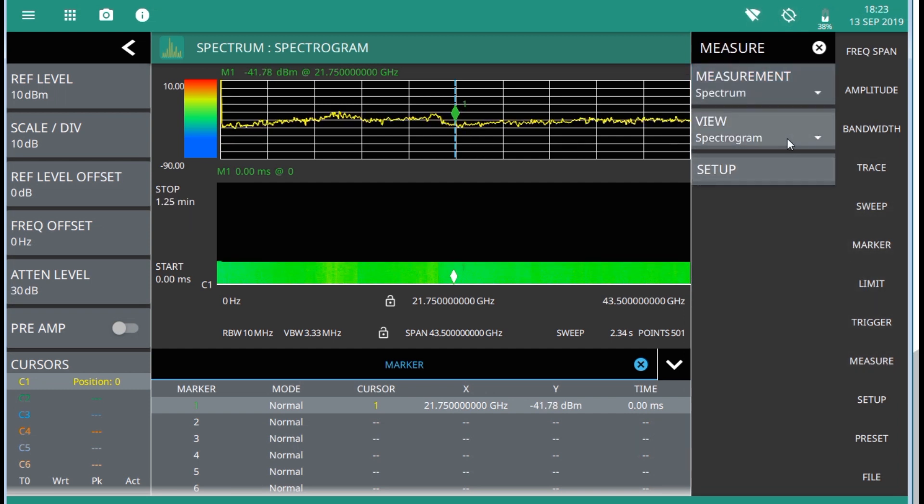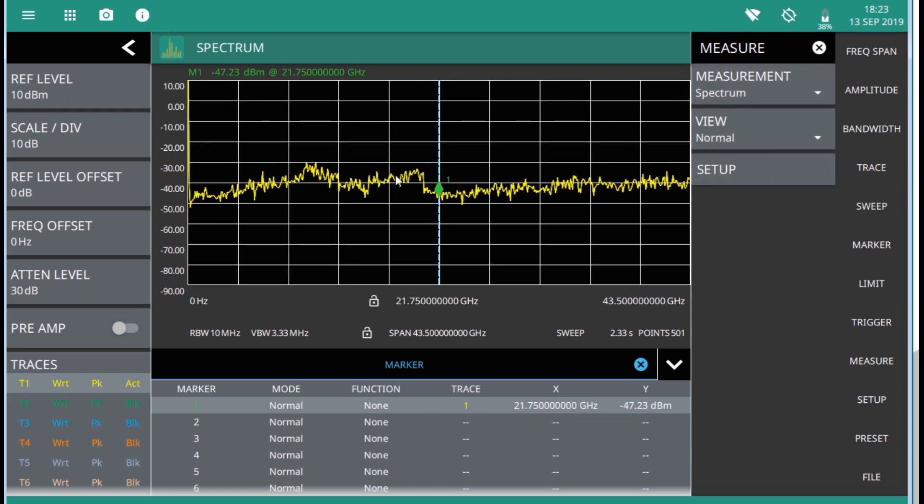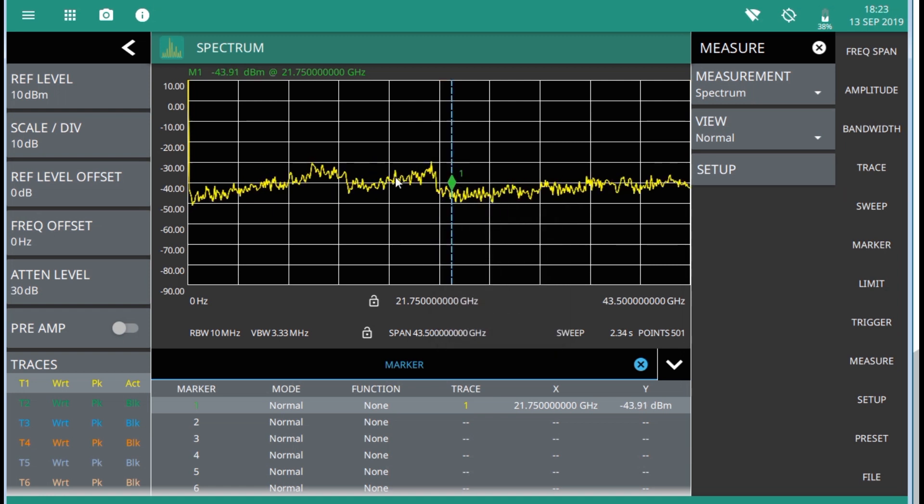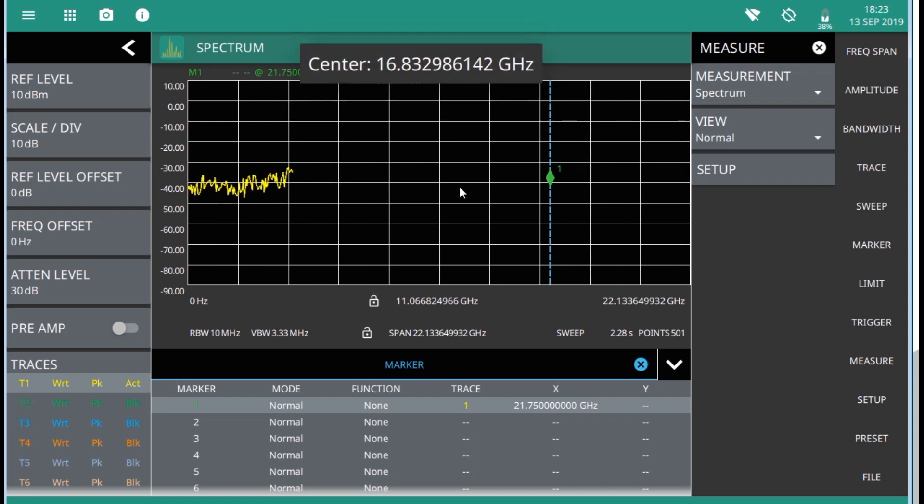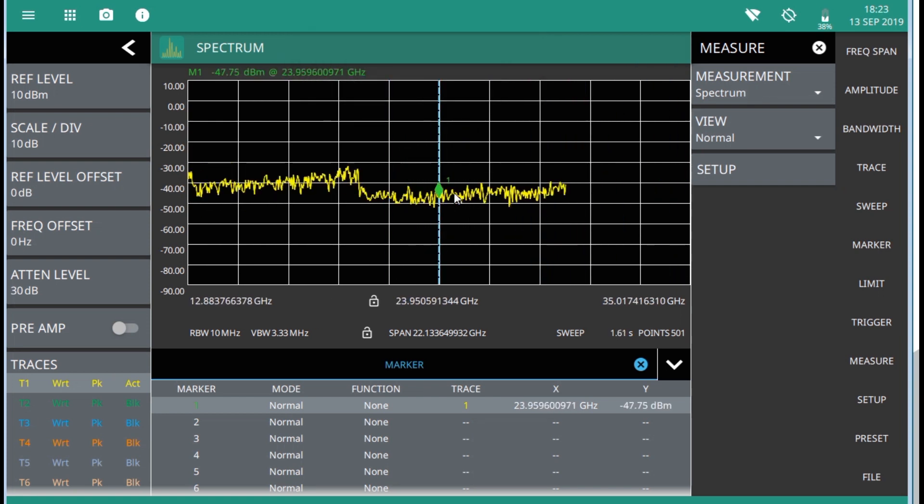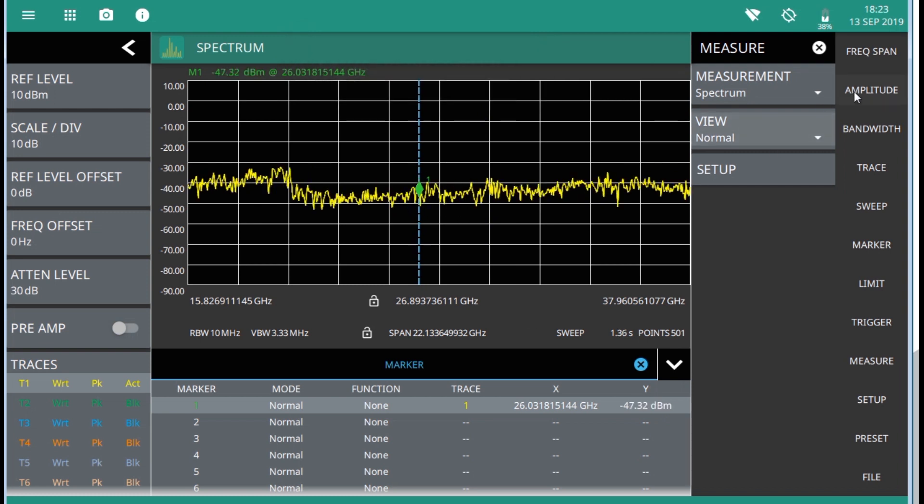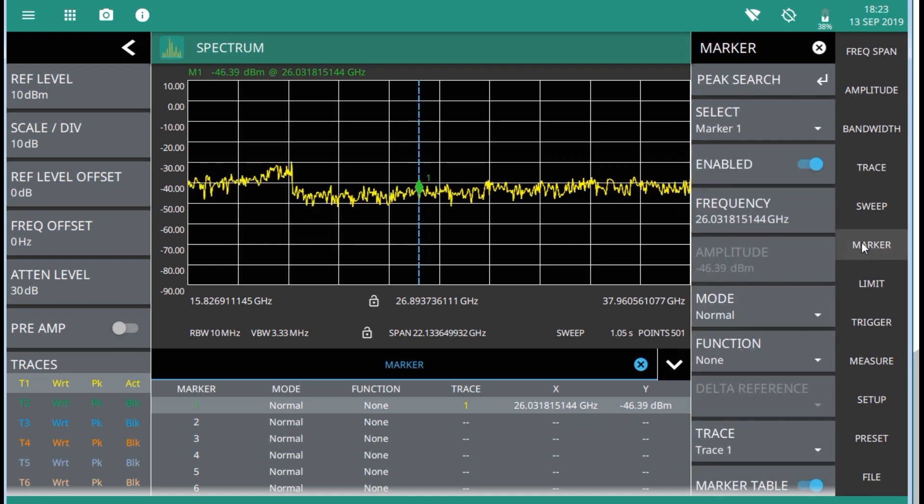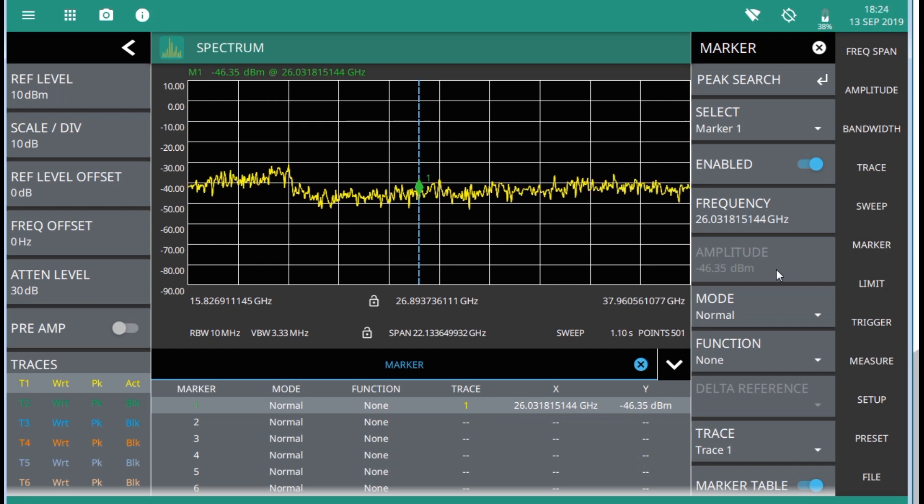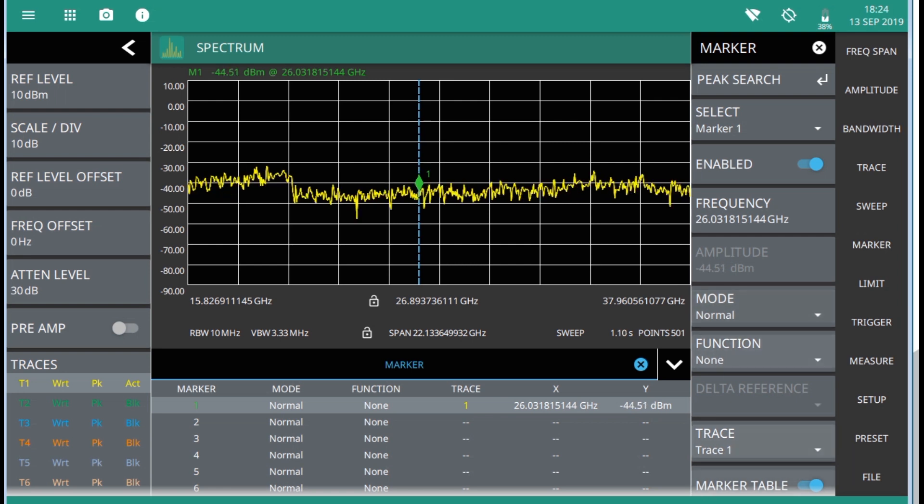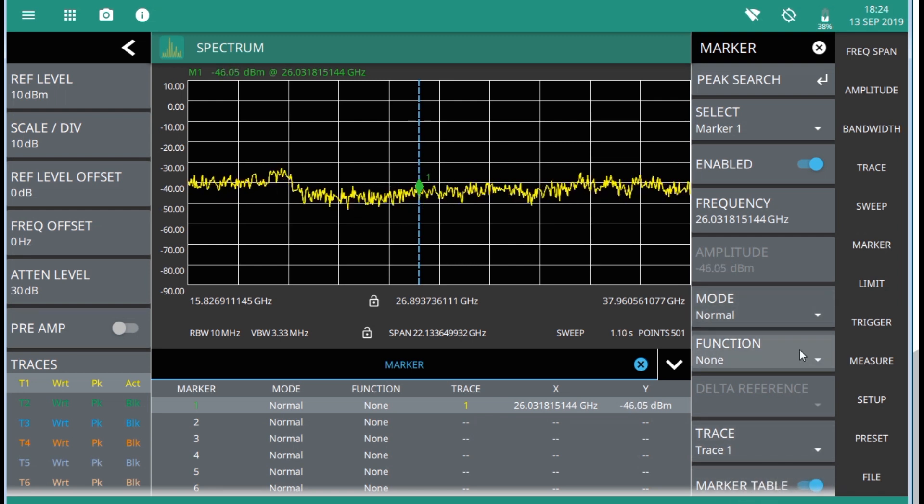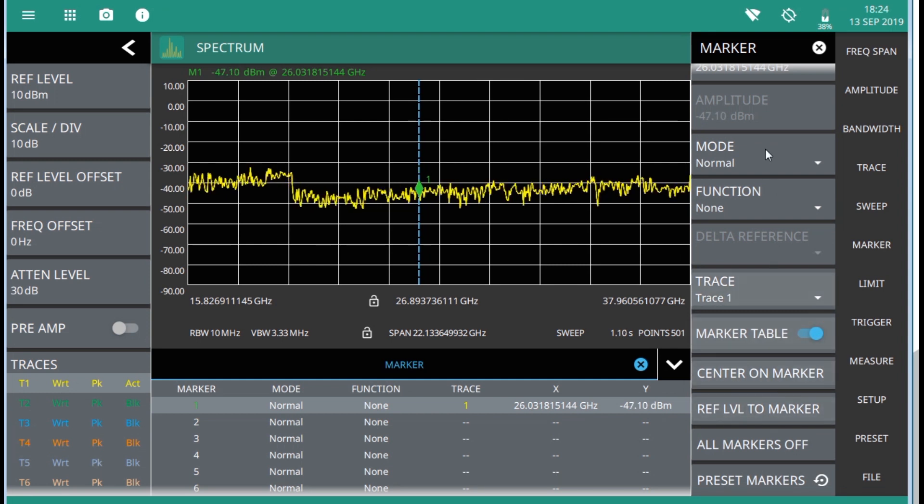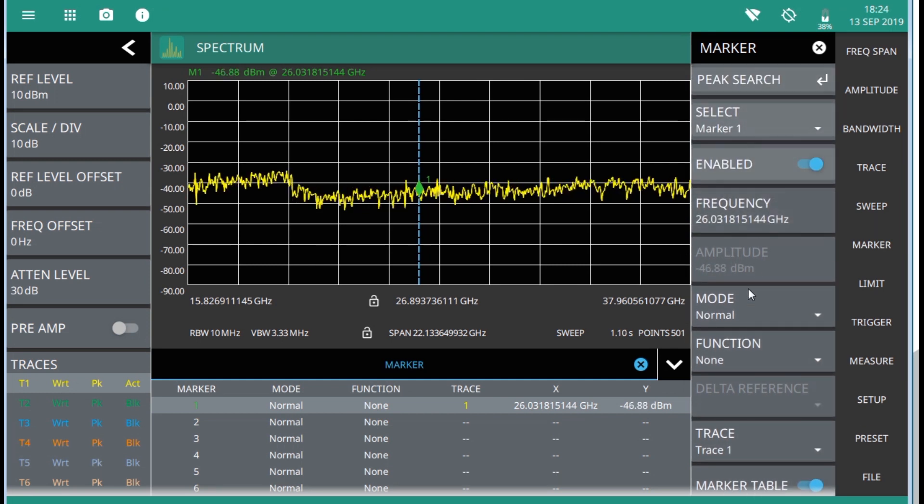FieldMaster Pro uses common touch gestures to achieve a variety of operations. These include interactions on hot areas by pressing, double pressing, dragging, or pinching. You can drag items such as markers, limit line nodes, and the center frequency by dragging the trace to the left or right. In some cases, menus, status panels, or other lists contain more information than can be displayed in the available area. In these cases, the top or bottom of the panel will have a fade to white appearance, as shown here. You can scroll the control to move it up or down and expose the hidden information.